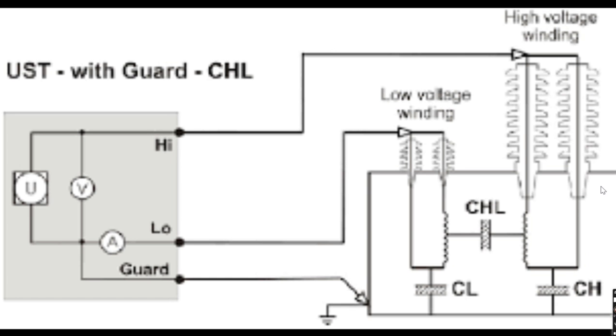In USTG mode, the guard cable of the kit is connected to the insulator flange of the CVT so that the leakage current flowing over the surface of the CVT should not be counted for the measurement of tan delta.